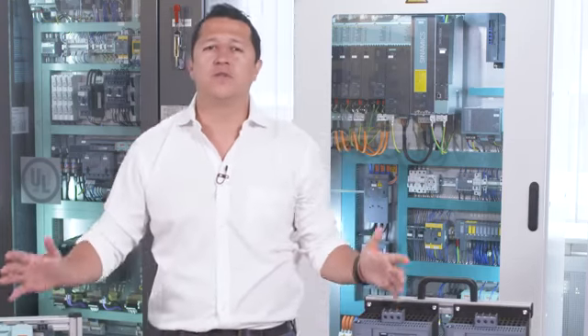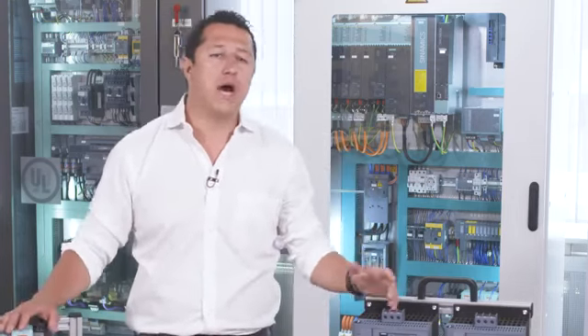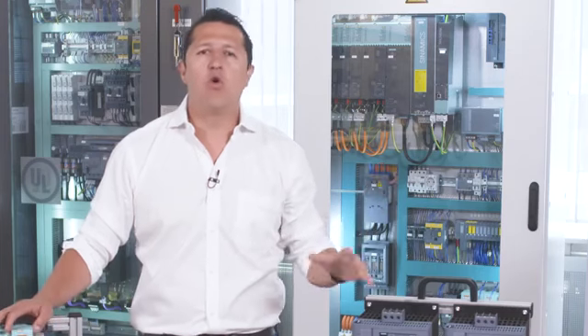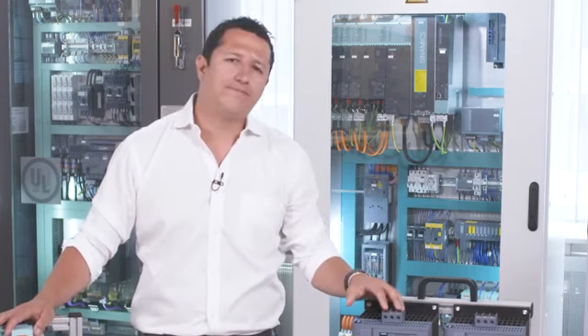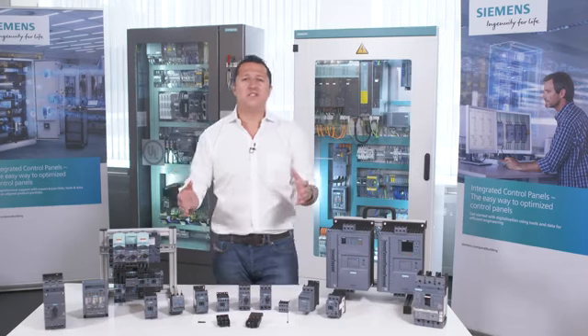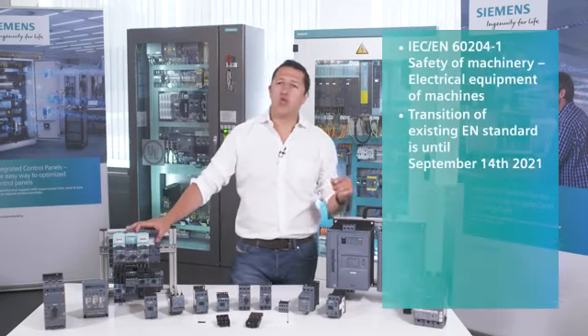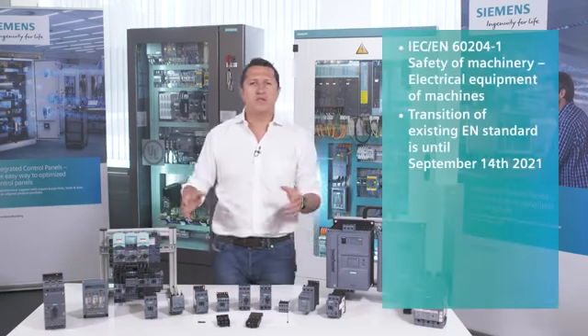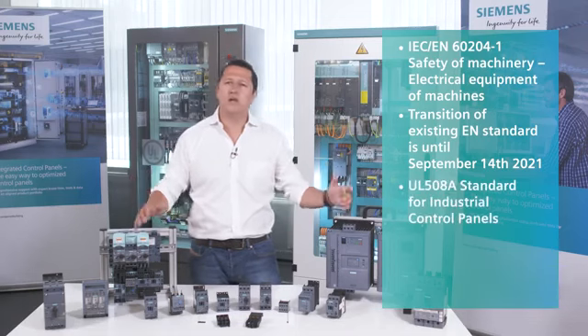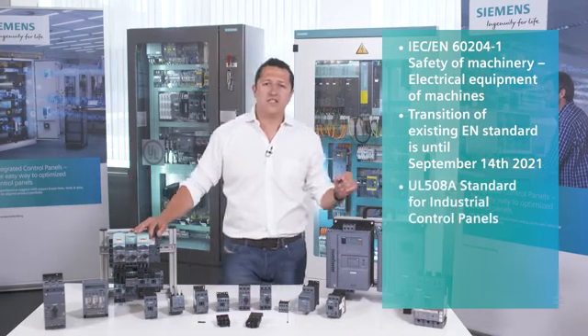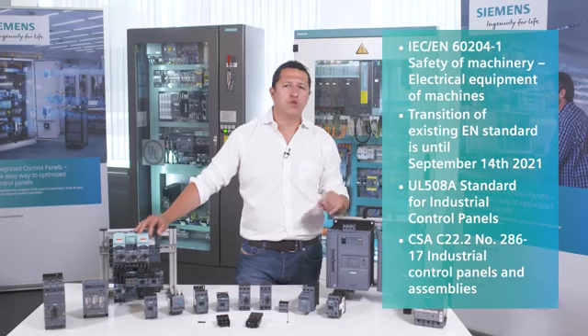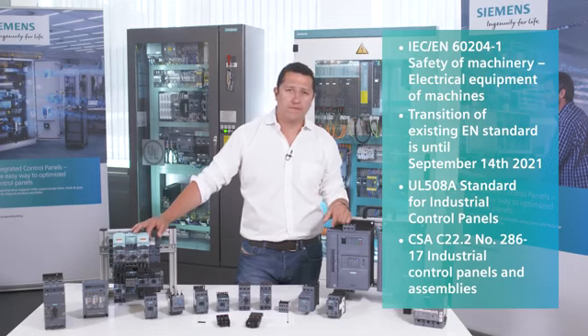short-circuit fault. When talking about control panels, you often hear or mention IEC, UL, or even CSA standards. In IEC, it's the IEC 60204-1. For the US, it is the UL 508A. And in Canada, the CSA C22.2 No. 286-17. These are the correct standards for industrial control panels.